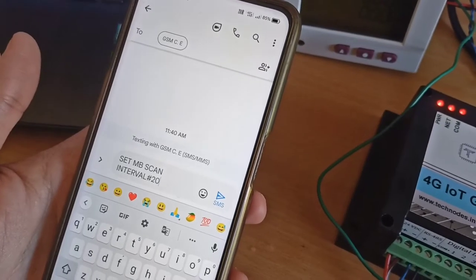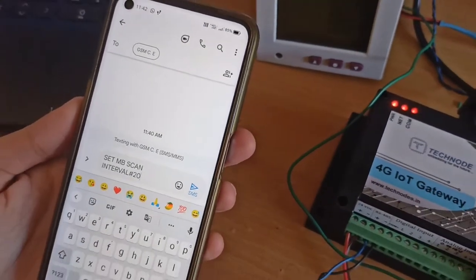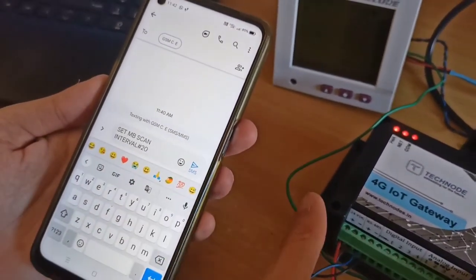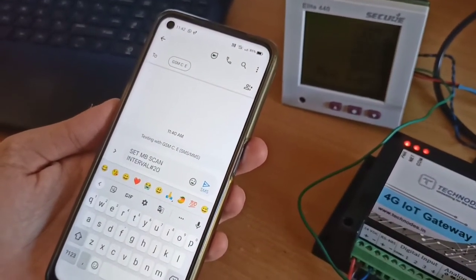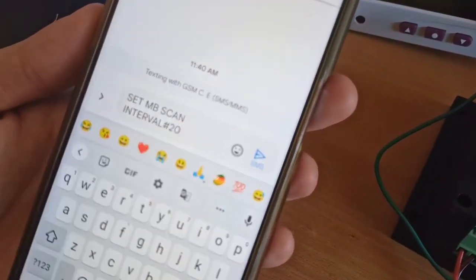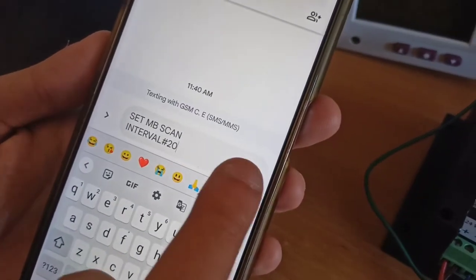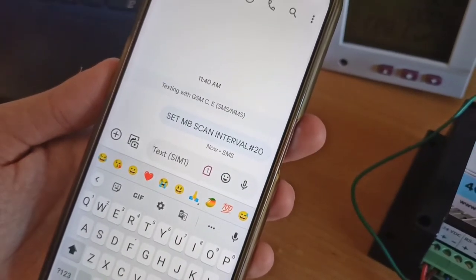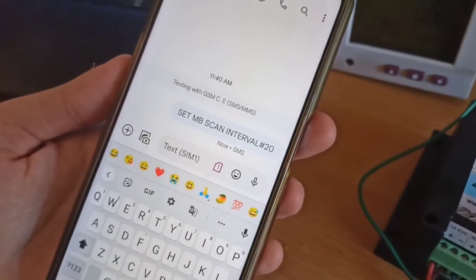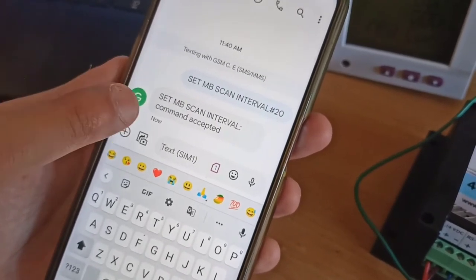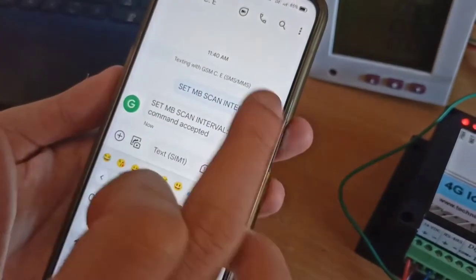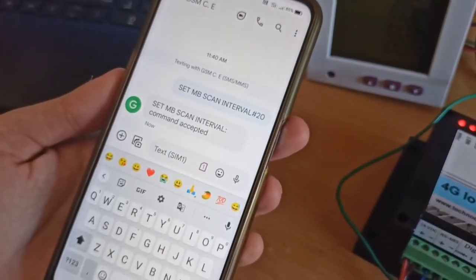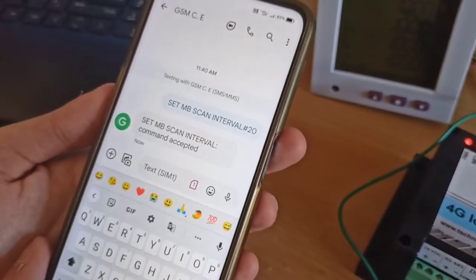So our gateway has one more feature: this gateway is also configurable via SMS. So even if the gateway is connected on site, you can remotely configure the gateway. So just for a demonstration purpose, I have typed one message that is 'set MB scan interval hash 20'. So I am just sending this message to our gateway. So I have sent this message and let's see what reply we get. So you can see 'set MB scan interval command accepted'. That means the Modbus scan interval is set to 20 seconds.